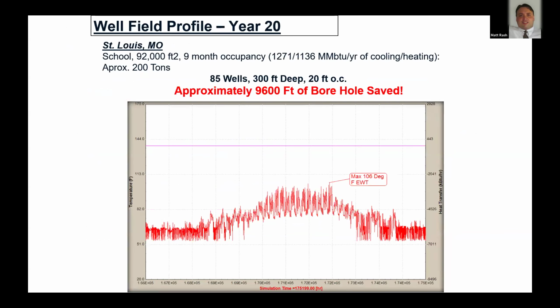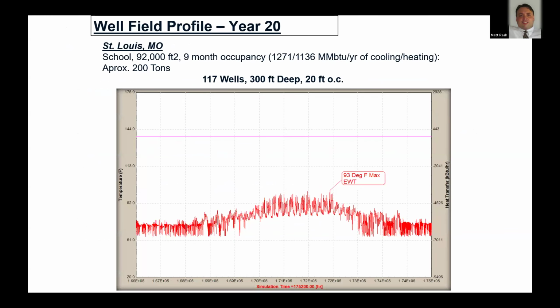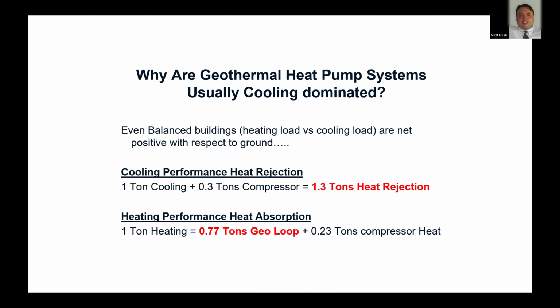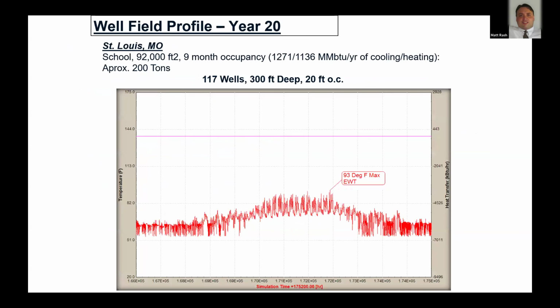One thing I would note is geothermal well fields tend to be cooling dominant, and that's just because of heat of compression. If we had a balanced building in terms of number of BTUs of cooling versus heating throughout the year, because of that heat of compression component, the well fields tend to be cooling dominant, even in more northern climates.